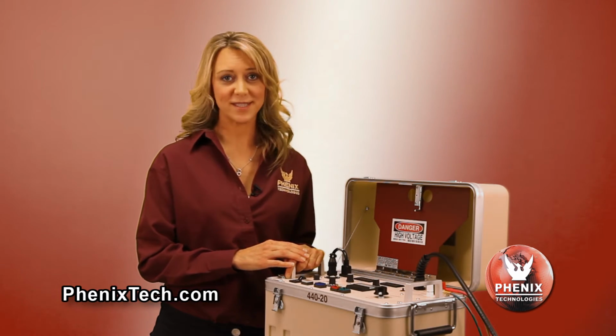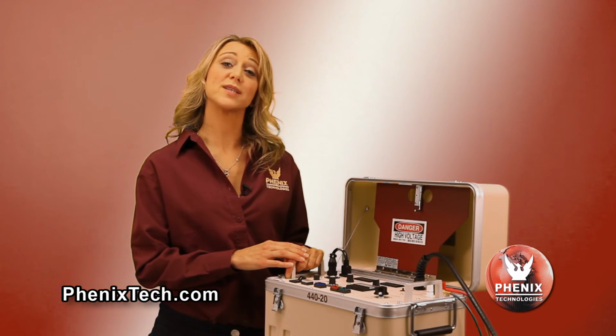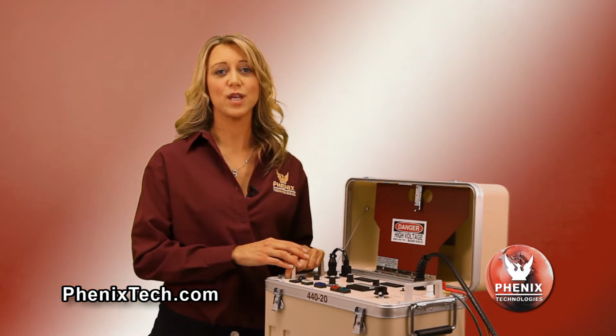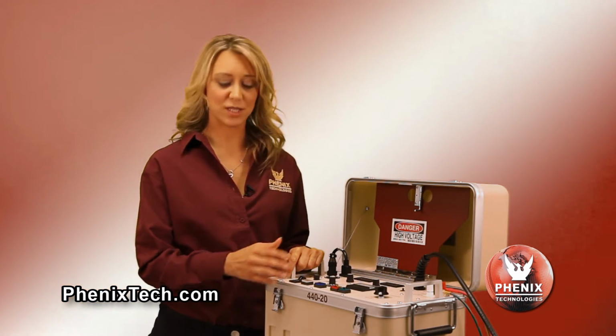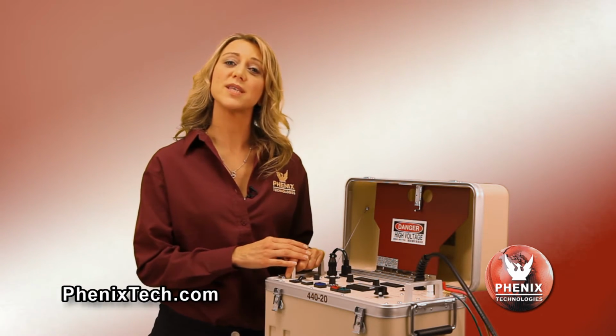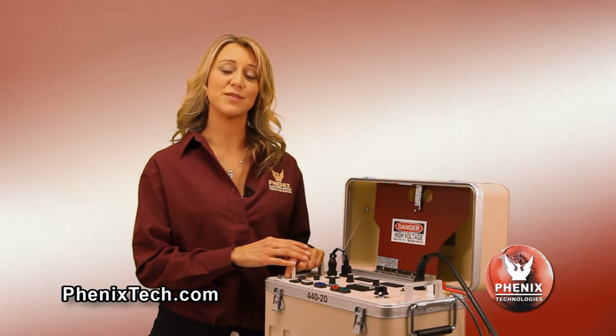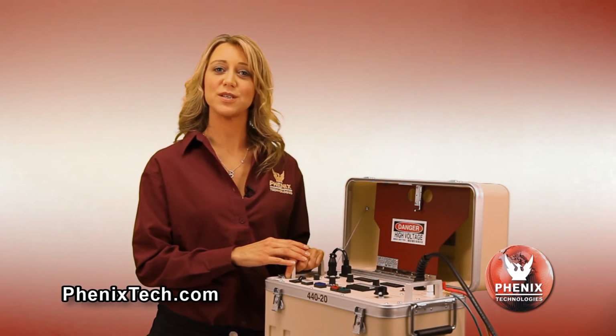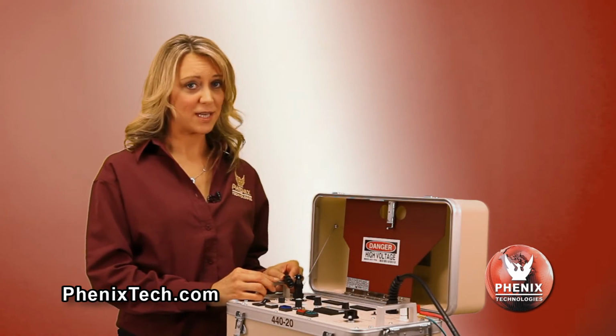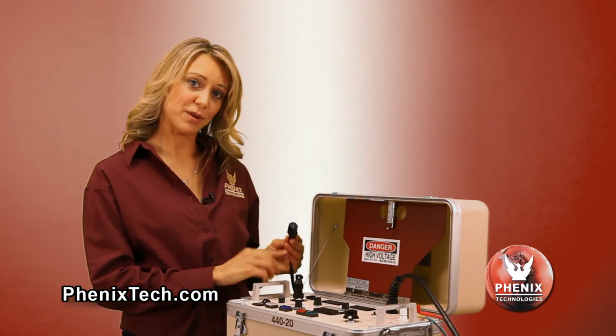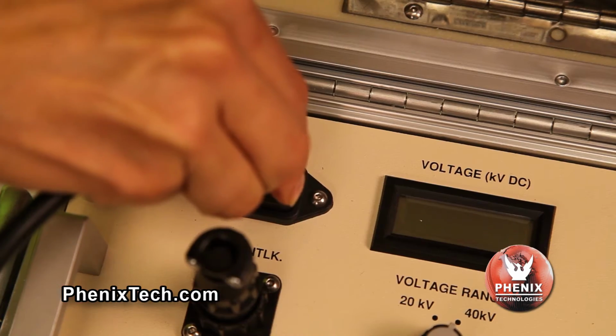Operation of these units is simple. We will go through an example of an actual test sequence using the model 440-20. All units have identical control and measurement features with the exception of meter ranges. The main difference between the units is output voltage, weight, and that the 120 kV and 160 kV units have separate high voltage tanks. To begin the test sequence, plug power input cable into test unit.